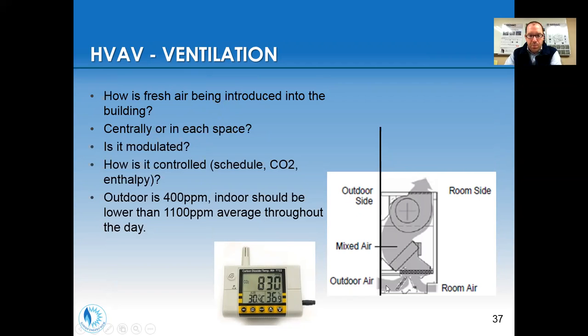So here's an example of an outside wall, and the outdoor air comes in through a louver and mixes with some room air. It's heated in the coil and then blown into the room. So make sure that this damper is working correctly, that it's connected correctly. Sometimes they're just manually set, and maybe take a handheld CO2 meter and check these rooms during high occupancy periods. You can get data logging CO2 meters that are not too expensive. In new construction or in major retrofits, you can retrofit these into the HVAC system so that it dynamically controls the outdoor air in the spaces based on the space CO2 set points.